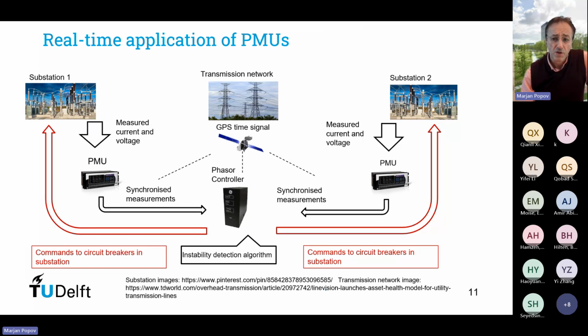So PMUs are normally installed in substations. They measure voltage and current phasors. They supply these voltage and current measurements through a phasor data concentrator, in this case to a phasor controller. And on the phasor controller, there are algorithms that run and are capable of detecting particular system anomalies. In this way, upon the occurrence of such anomalies, responsible circuit breakers can be switched off.